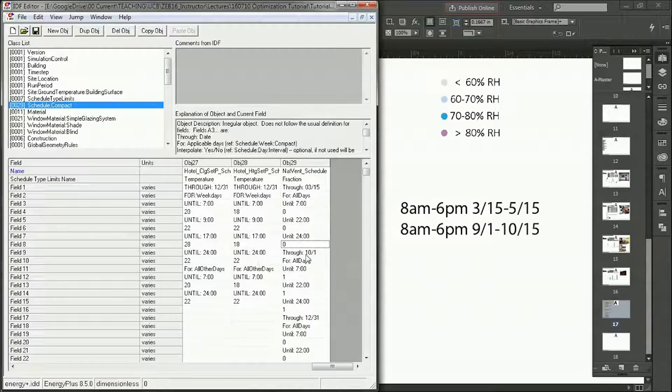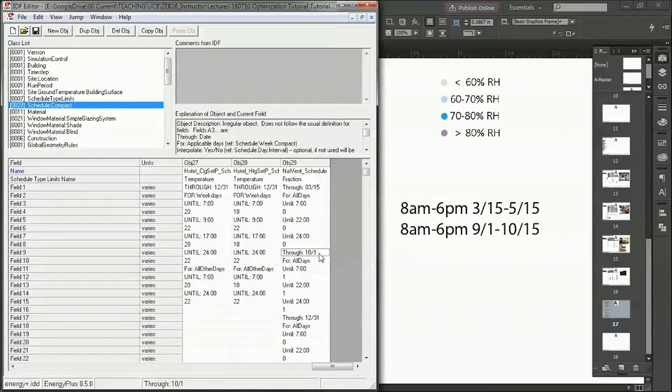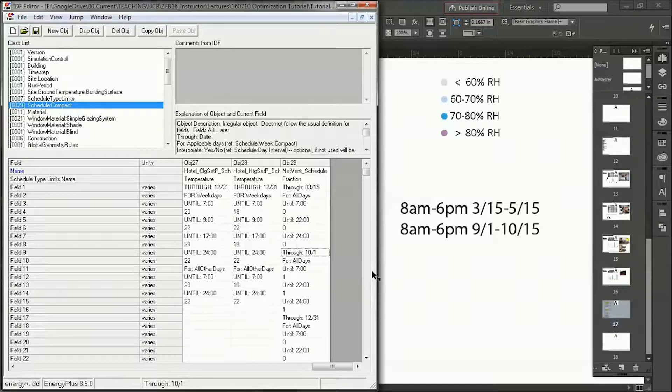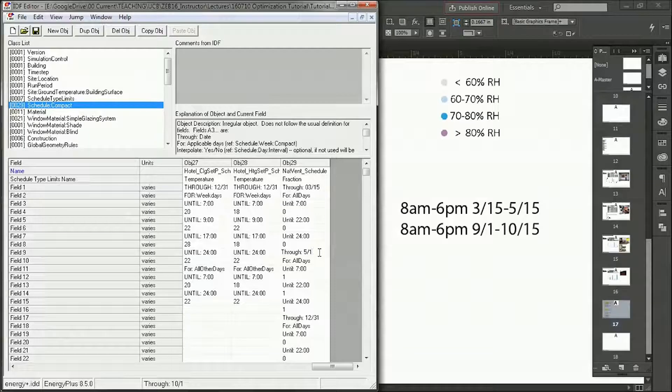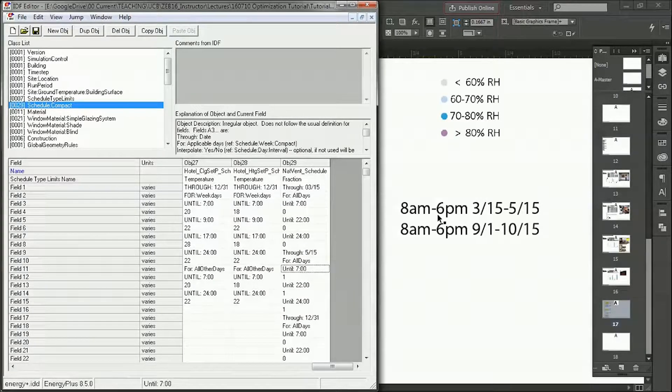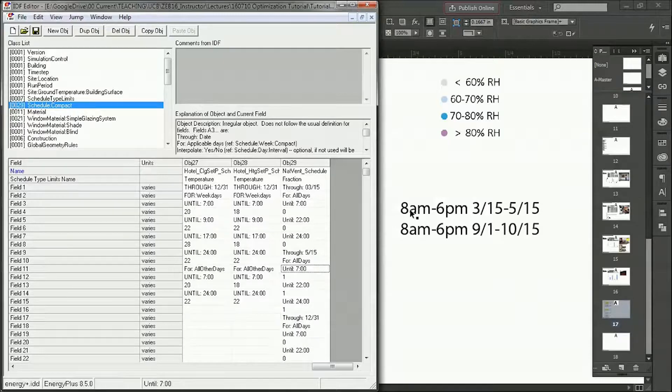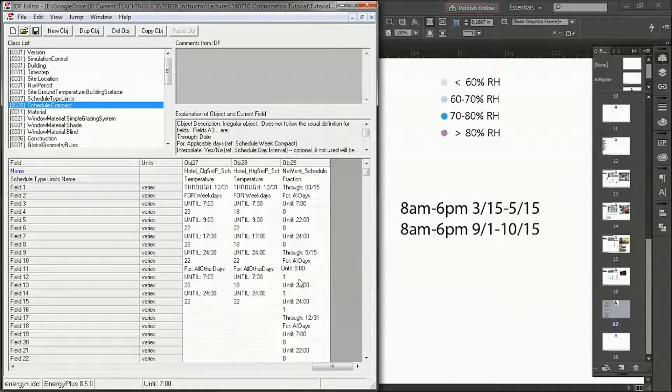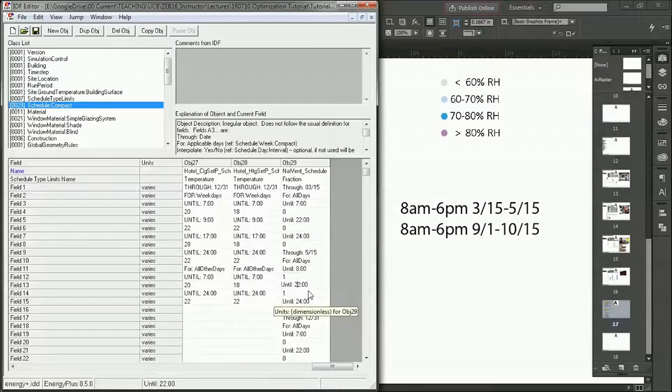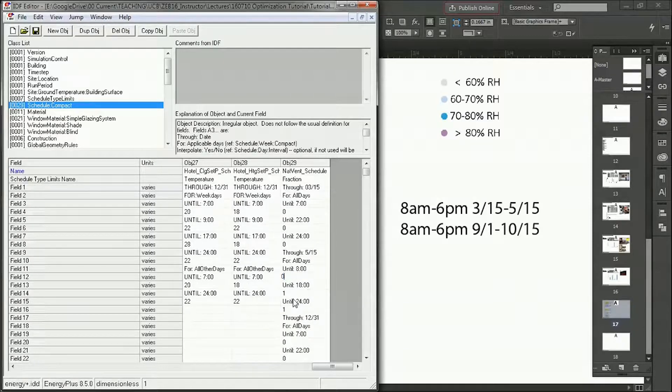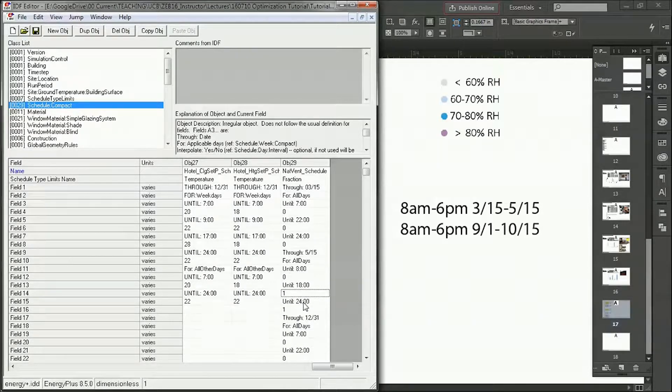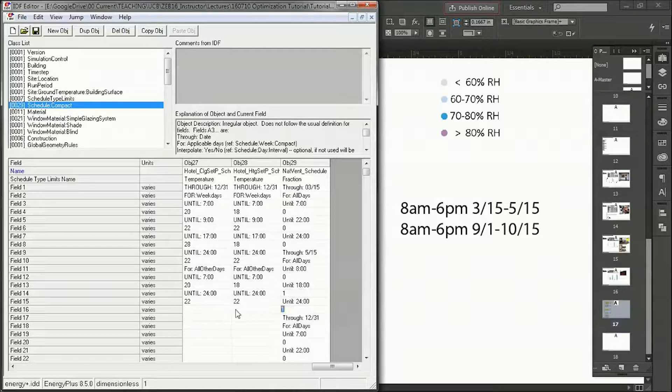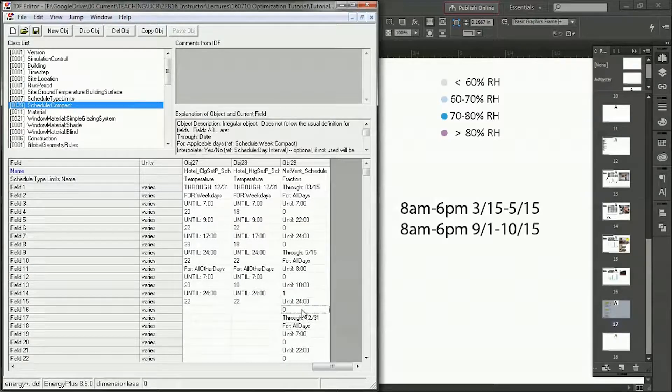And then through October 1st, now we actually want May 15th here, so we're going to change this to May 15th for all days. And now we want it from 8 a.m. to 6 p.m. So I'm going to change 7 to 8 and 22 to 18. And we don't want it from midnight to 8. We do from 8 to 6 or 18. And then we don't want any ventilation from 6 p.m. to midnight, so that'll be 0.